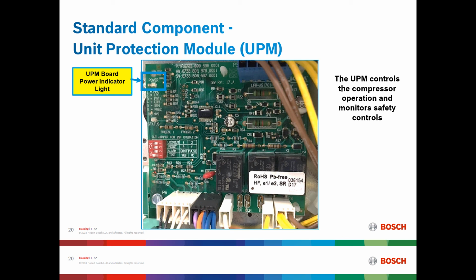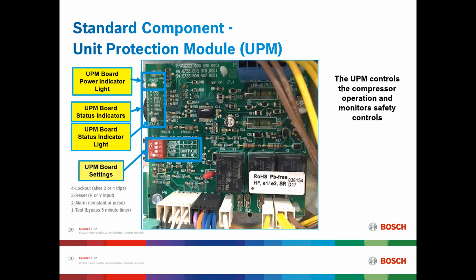The top left, it will have a UPM board power indicator light. It also has board status indicators because it is self-diagnostic for easy repair, and a status indicator light to help the contractor or technician in the field. On the lower left, it will have UPM board settings that refer to lockout, reset, alarm, and test bypass. This particular board features an alarm output and a short cycling feature, a 5-minute delay, random unit start feature, and brownout or low voltage protection.